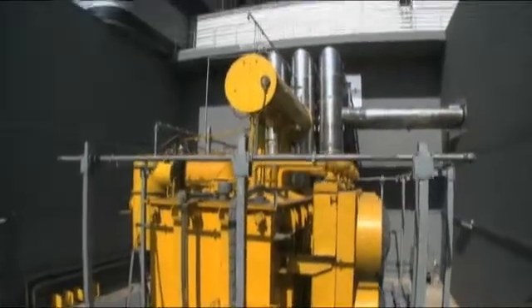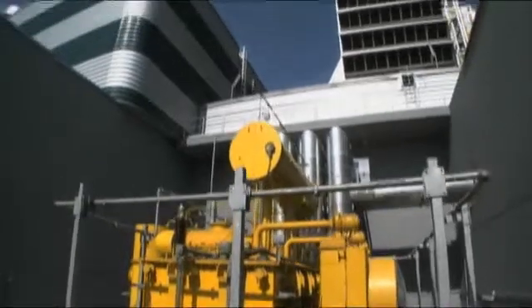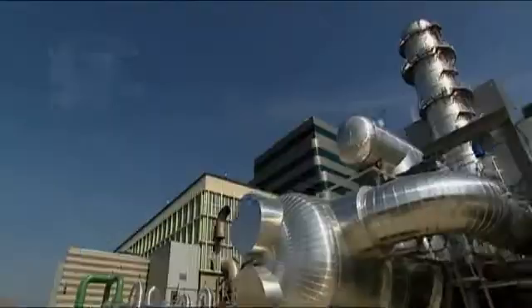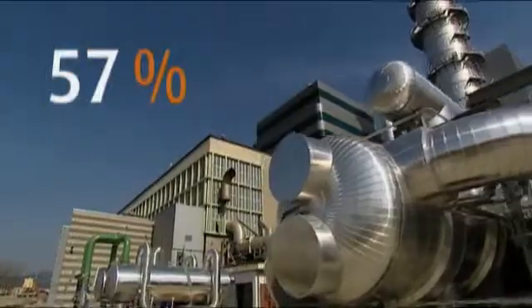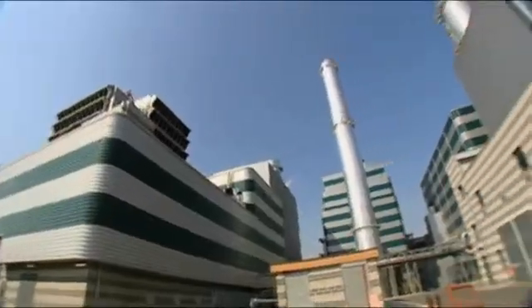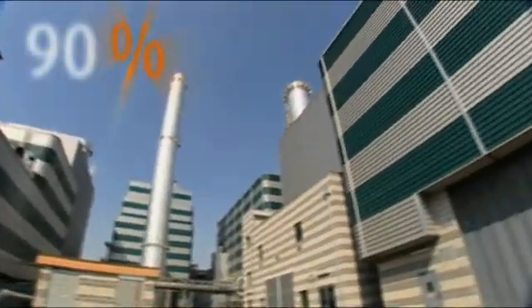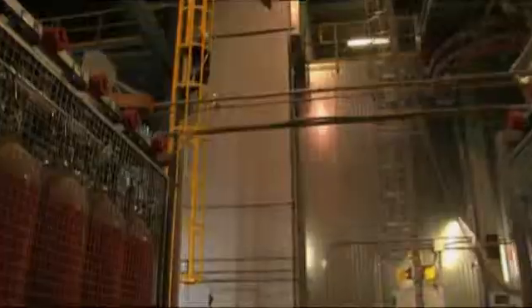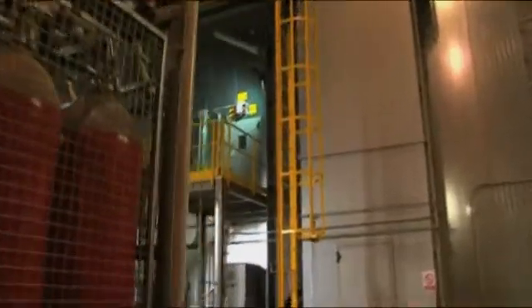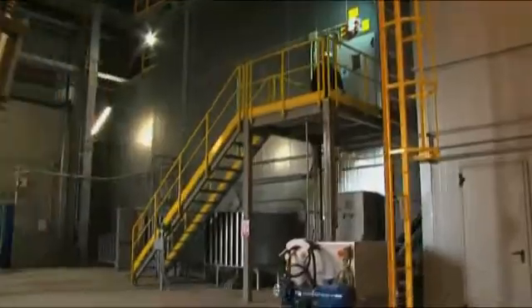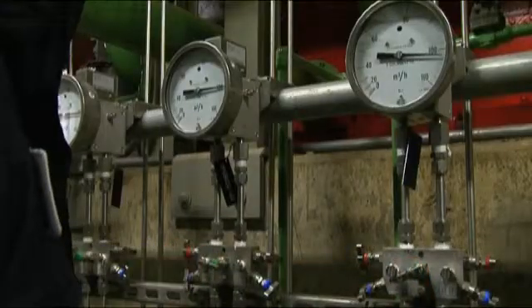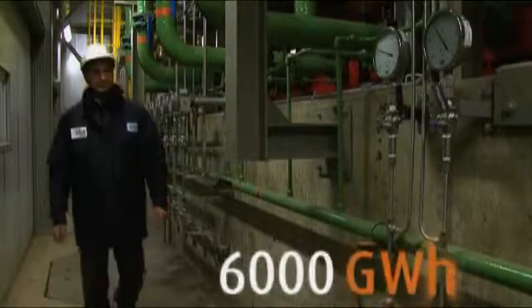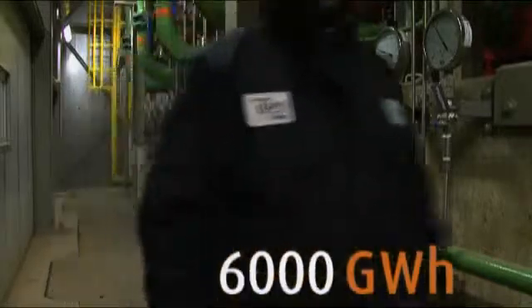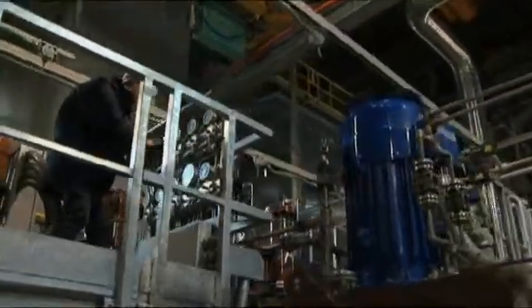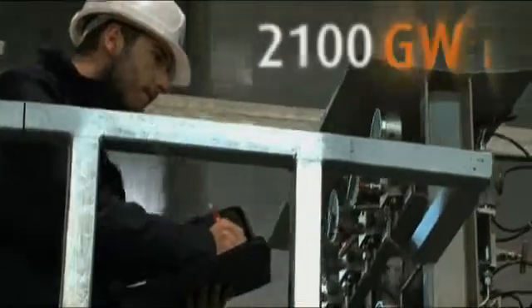In electricity mode, the Iren Energia cogenerators have an efficiency of 57% compared to a national average of roughly 46%, while they reach 90% when in cogeneration mode. On the whole, they boast an annual electrical capacity of over 6,000 gigawatt hours, which is twice Turin's energy demand, and an annual thermal capacity of 2,100 thermal gigawatt hours for district heating.